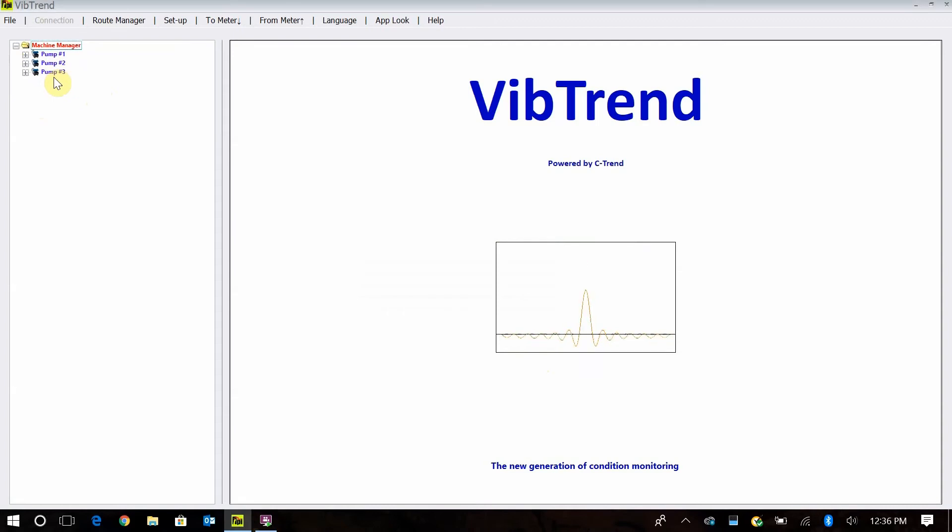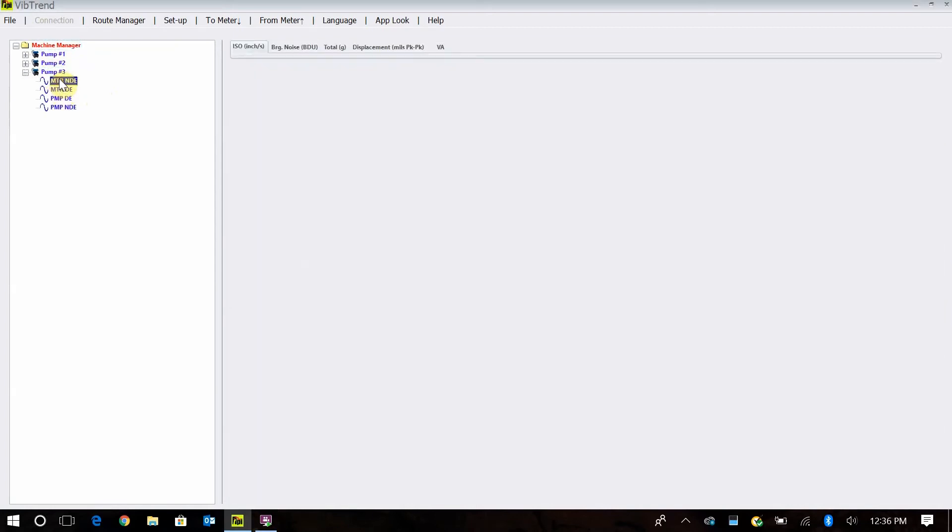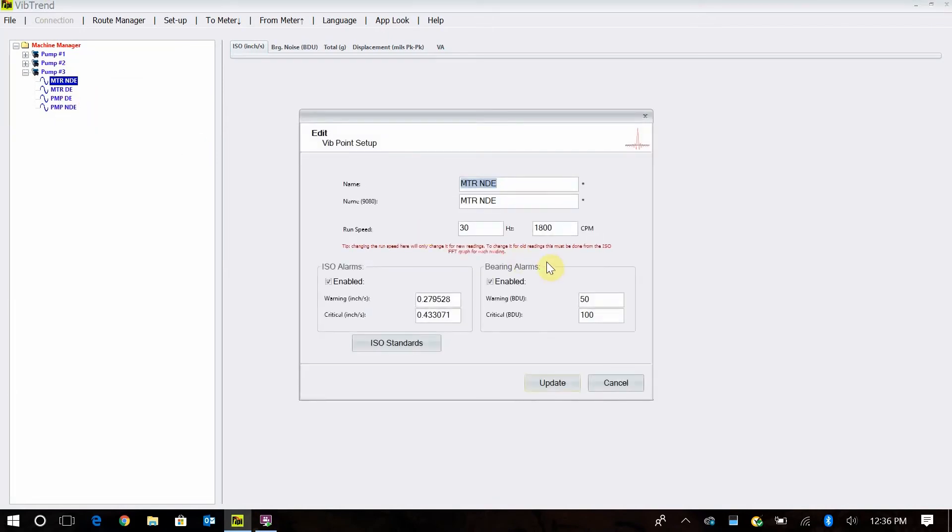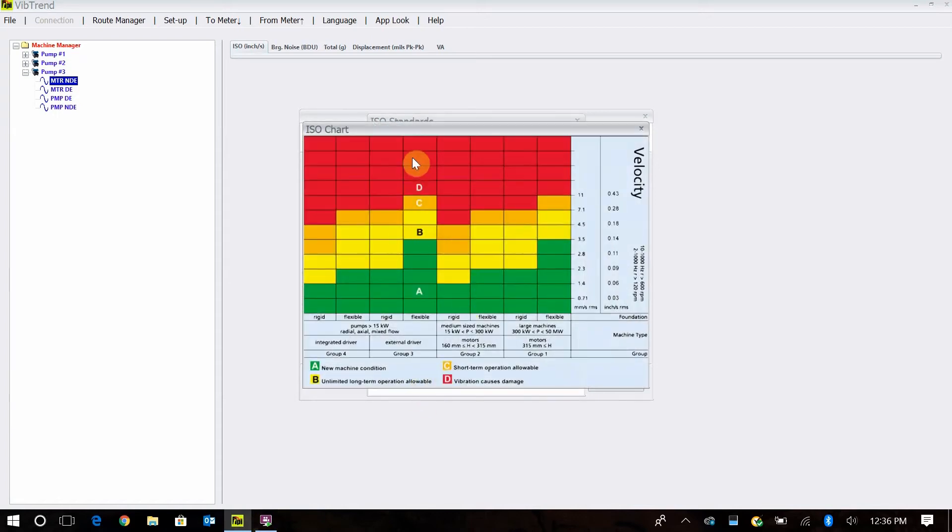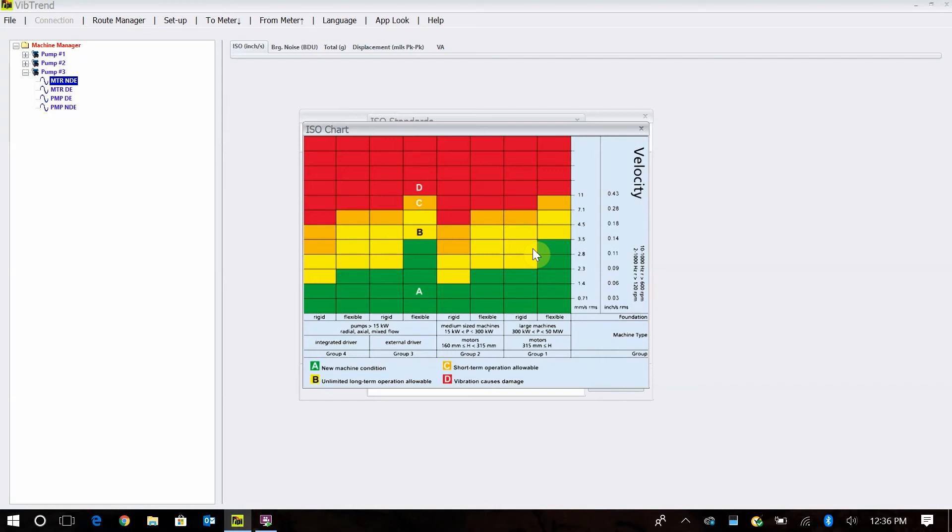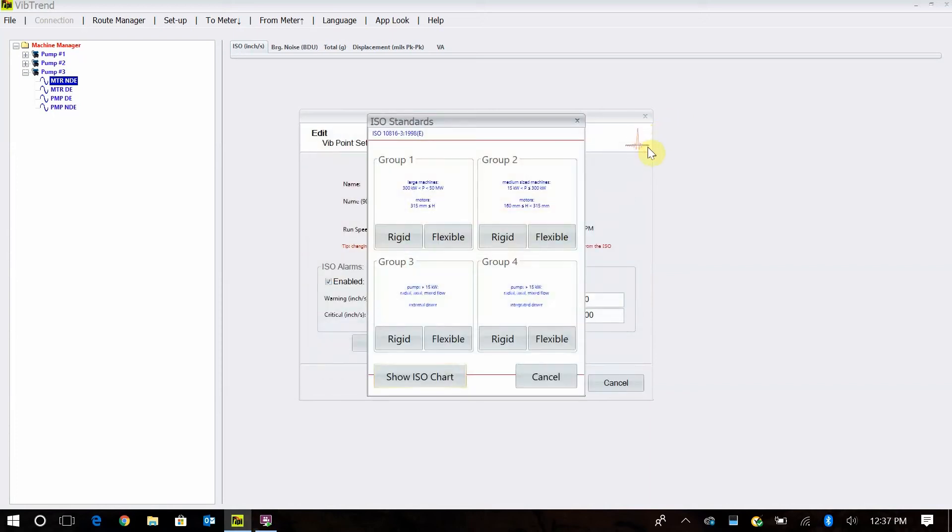You saw the ISO alarm levels there when we were setting these up. When I go in here and edit, if you have any questions on this, there's the ISO chart. You can click on the ISO chart and it shows you where the values are both in millimeters per second and inches per second and where those alarms should be set. Good rule of thumb is to walk out with your vibration meter, take some readings off your machine, and just kind of see where they're running. Are they running at 0.09 inches per second, 0.1 inch per second, and then set the values just above that. But the whole idea is to get all your vibration levels running as low as possible, because the less vibration you have in the machine, the longer the machine is going to last. That's under your ISO chart if you want to see where the alarm levels are for the different ISO vibration levels.